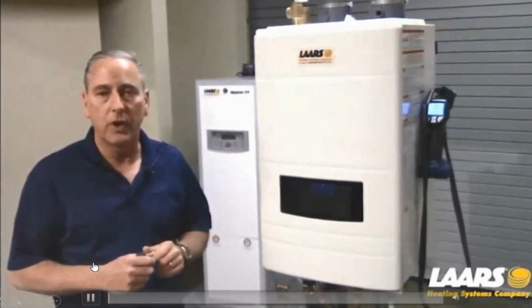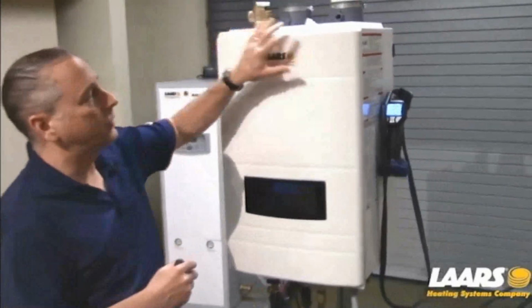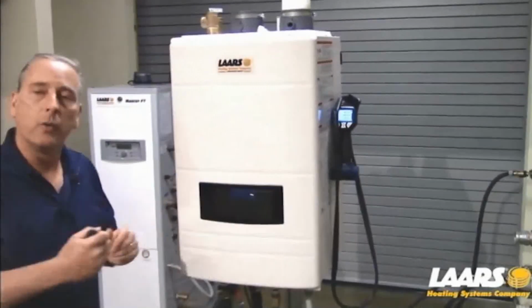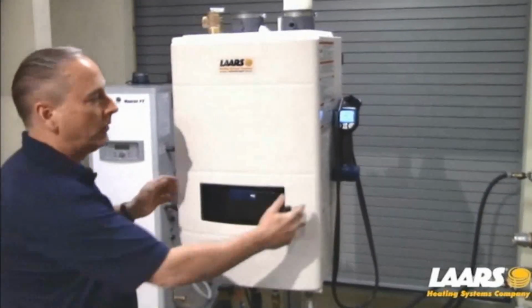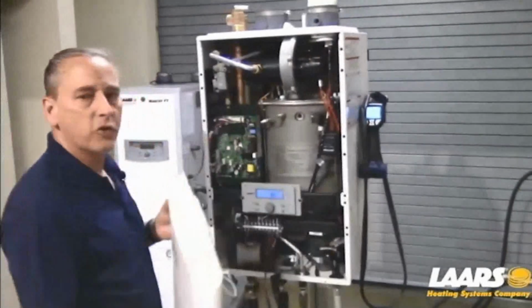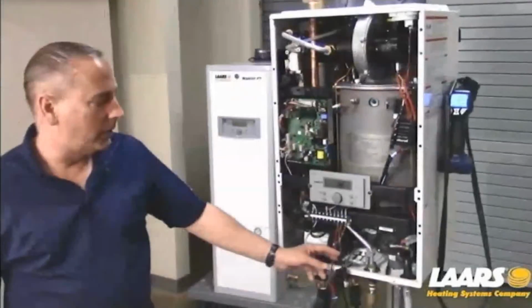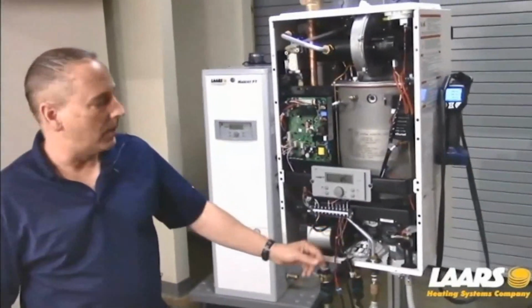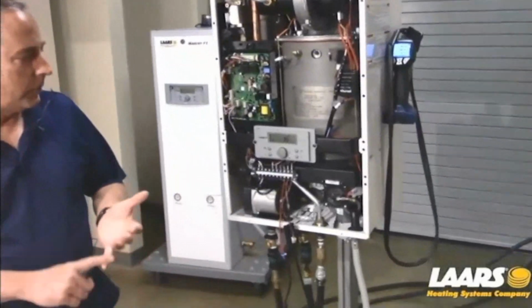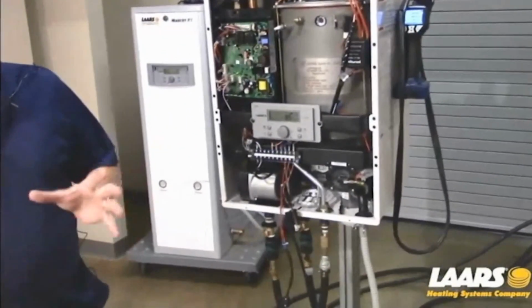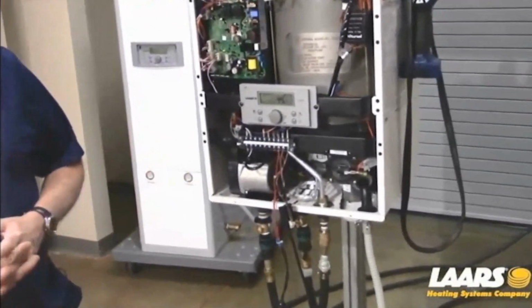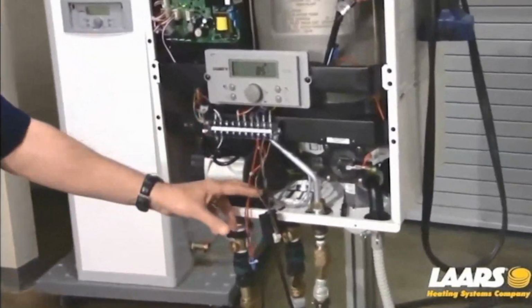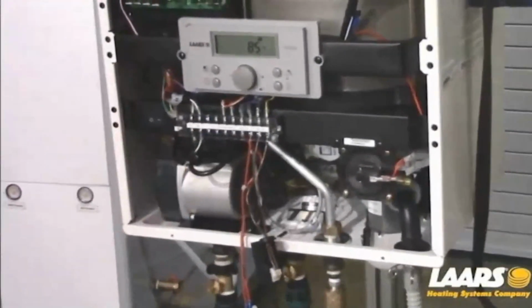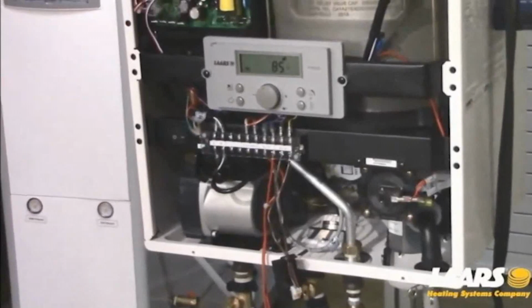First thing we're going to do is remove the cover. There are 4 screws, 2 on the top, 2 on the bottom. I've already removed those for the demonstration, so I'm simply going to lift the cover out of position. All right, so the next thing we want to do is disconnect the outdoor sensor wire. And the reason is, obviously, for example, like today, it's above 70 degrees and I'm above my warm weather shutdown, so even giving the boiler a call for heat will not allow it to operate. So we can get in and do combustion setup.